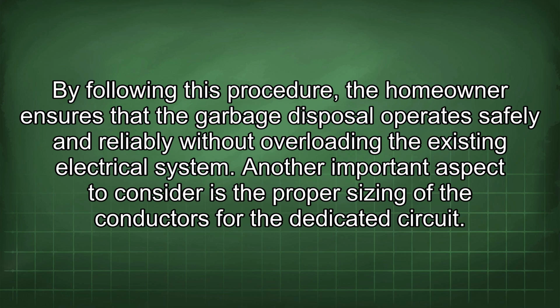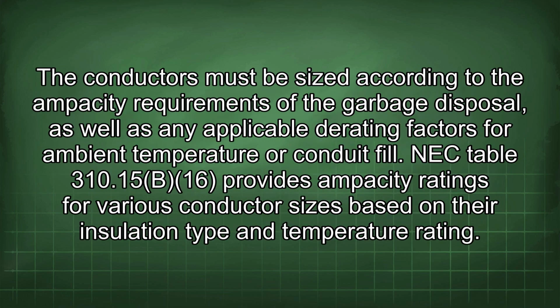system. Another important aspect to consider is the proper sizing of the conductors for the dedicated circuit. The conductors must be sized according to the ampacity requirements of the garbage disposal, as well as any applicable derating factors for ambient temperature and conduit fill. NEC Table 310.15(B)(16) provides ampacity ratings for various conductor sizes based on their insulation type and temperature rating.